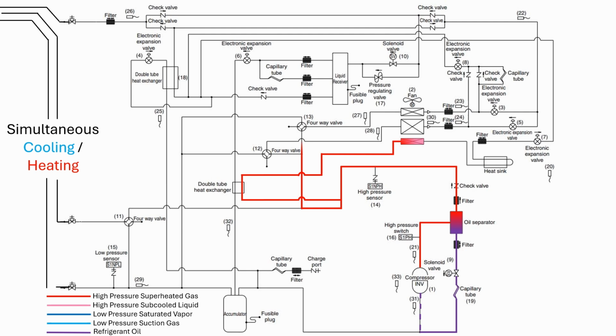So the high-pressure superheated vapor is also routed to that section of the coil where it too is subcooled into a liquid. The next 4-way valve will be shifted to direct the high-pressure superheated vapor indoors to the units that are calling for heat.